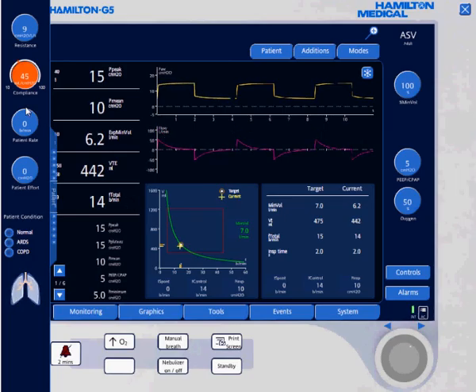I'm going to decrease compliance down a little more by 5 centimeters of water, so now compliance is 45. The new target tidal volume is dropping and will be approximately 463 — only 6.6 cc per kilogram of ideal body weight. For a patient with ARDS, this would probably be fine. However, for a patient that's post-op, they could be very hypoxic.